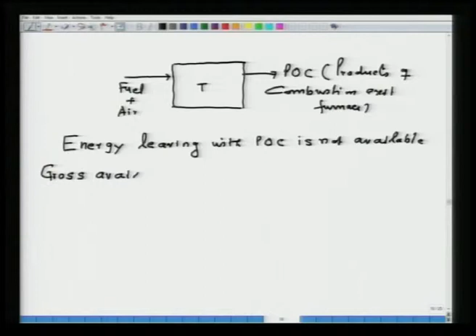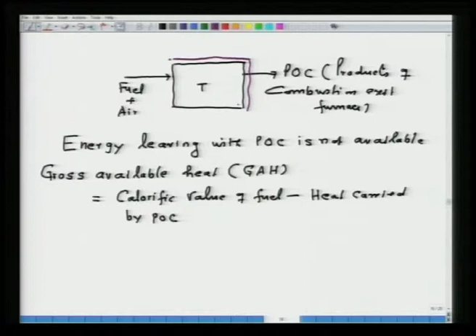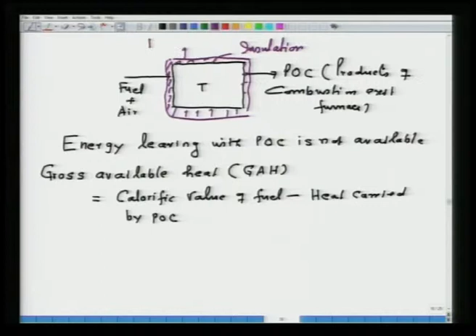Therefore, we can now define two important parameters. One, we say gross available heat, which I will call GAH, that is equal to the calorific value of fuel minus the heat carried by products of combustion. There is also an important term here, because when you construct the thermal enclosure, you put insulation here. So, this is an insulating wall, and through the insulation there will also be heat losses. Then another term is defined, that is called net available heat.